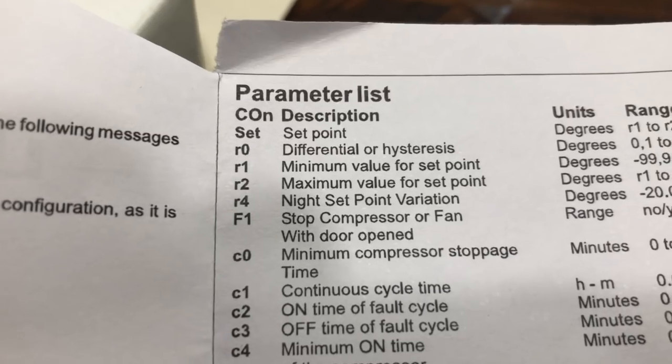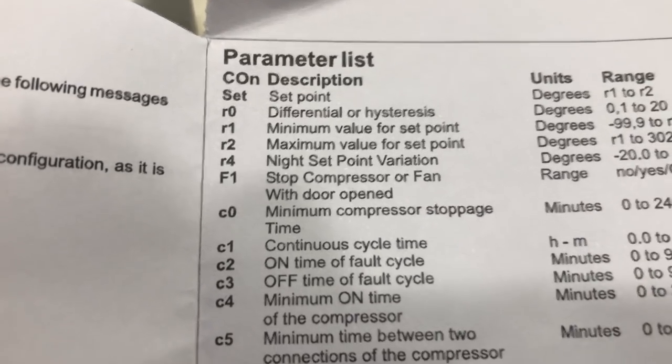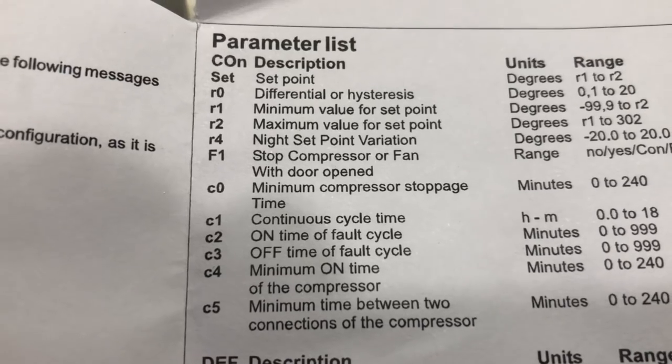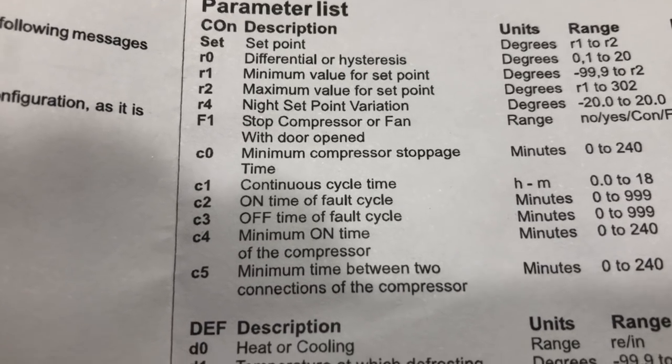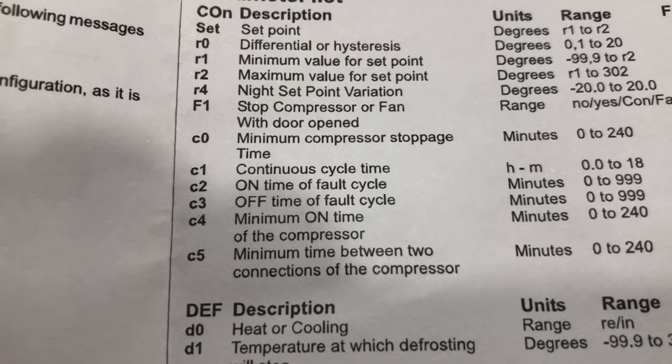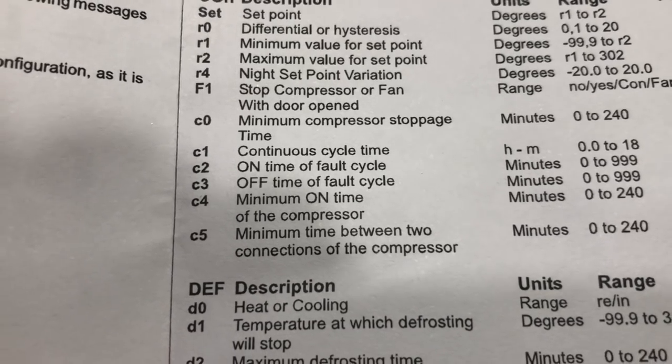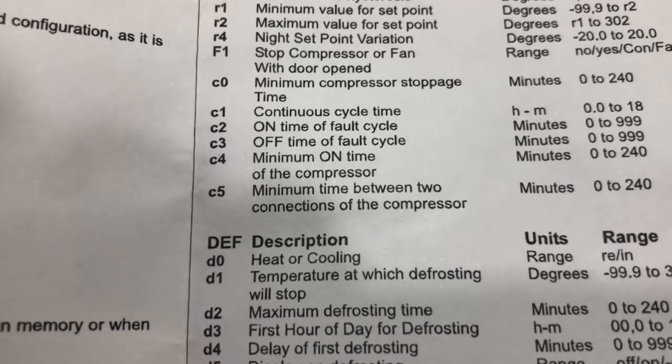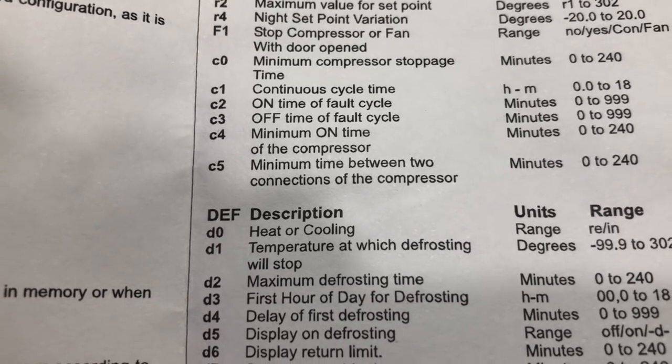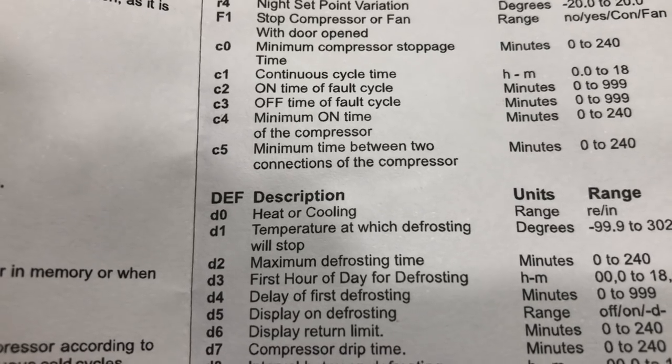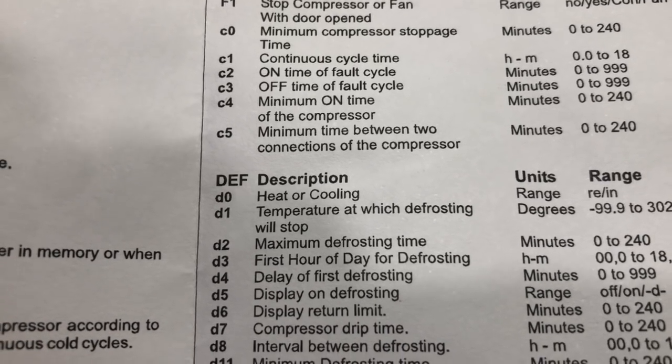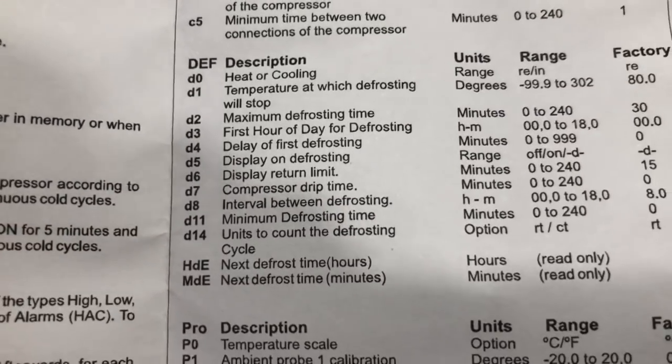And then you have all these subcodes. This is a list of your parameter subcodes. So it'll start off with CON, and that'll give you your set point, your differential, minimum value, maximum value, night set point variation, stop compressor or fan with door open, minimum compressor stoppage time, continuous cycle time, on time of fault cycle, off time of fault cycle, minimum on time of the compressor, minimum time between two connections of the compressor.